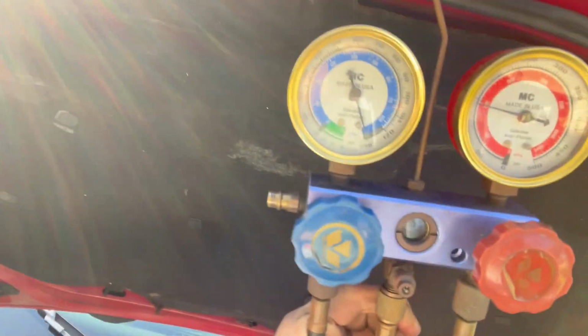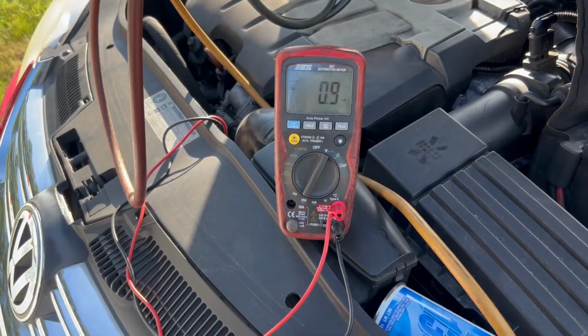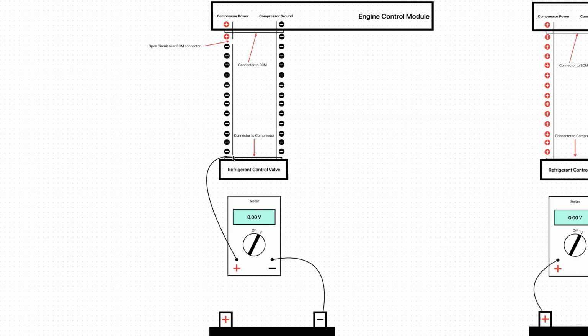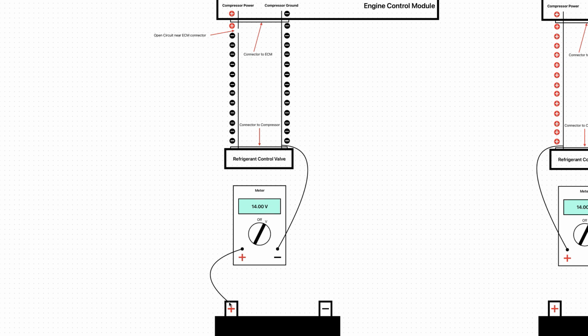And simultaneously, we're going to look at the refrigerant pressures and make sure that those are also not doing anything while the computer is commanding this compressor on, sampling the voltage and making sure the circuit's intact all the way to the compressor valve itself. With that multi-dimensional approach, we can basically know everything we need to know in one shot.